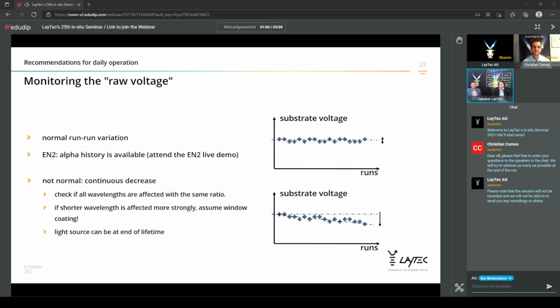Or a light source can also be at the end of its lifetime. It's LED based. The lifetime is several years, but after several years there will be an end of lifetime. We have seen that not all of you are using the three wavelengths at the same time. We found in the field that somebody didn't recognize that one wavelength was already missing. Unfortunately, it was the one he is not using.